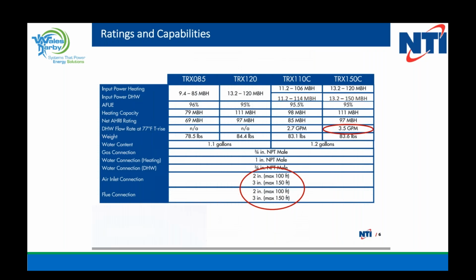So here, what we're showing you is our capacities on the 85 and the 120. You can see that sliding scale, so how low these boilers can get to. Because micro zones, this is something that John always talks about a lot in his hydronic classes, because some guys will say, hey, I don't have to worry about sizing a condensing boiler because they modulate. Well, yes, you do, especially if you're going to have those micro zones. So this is a big deal. And you can see on the Combi side, the output at a 77-degree temperature rise, how many GPM it will produce. Jim, just to touch on that for a minute, you're right. I do hammer that quite a bit on the modulating boilers.